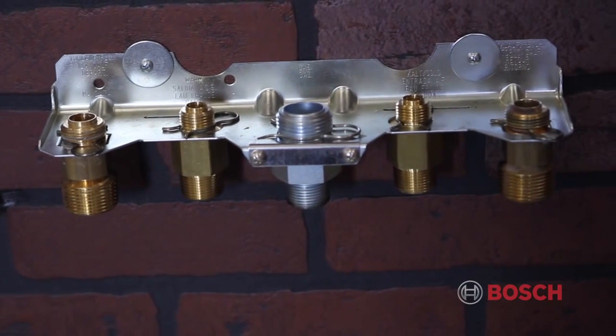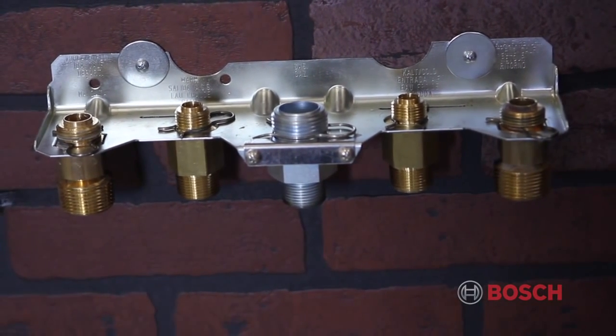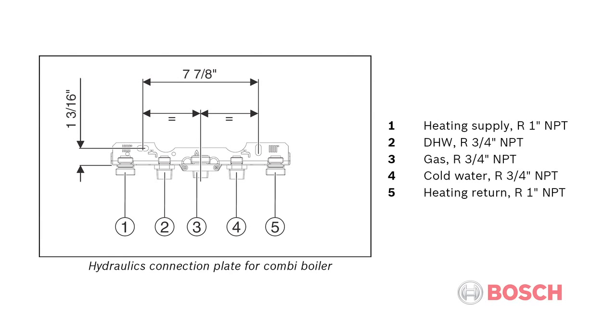The hydronics connection plate for the combi boiler has 5 connections. Starting from the left, first is your heating supply, 1-inch NPT connection. Second is your domestic hot water, 3/4 inch NPT connection. Third, and in the middle, is your gas, 3/4 inch NPT connection. Fourth, your cold water, 3/4 inch NPT connection. And the fifth is your heating return, 1-inch NPT connection.